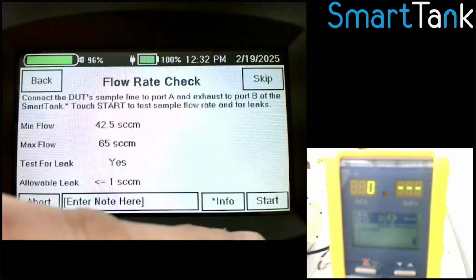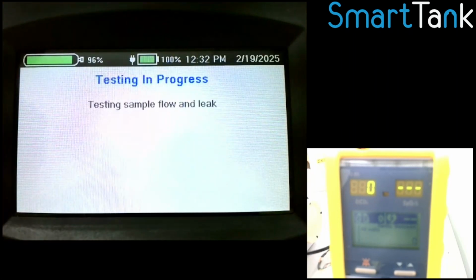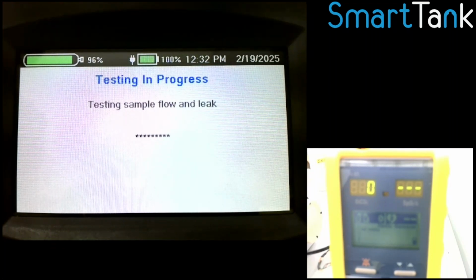So remember, I had the sample line and the exhaust hooked up. I'm going to hit start. This will take about 12 seconds. The built-in flow meter is very accurate. It can measure all the way down to about 0.5 milliliter a minute. All the way up over 200. And so it will go ahead and check the flow rate of the device.